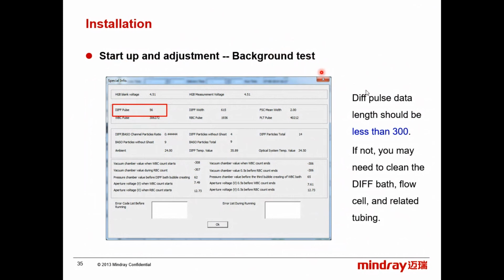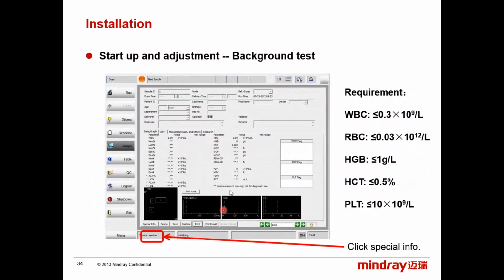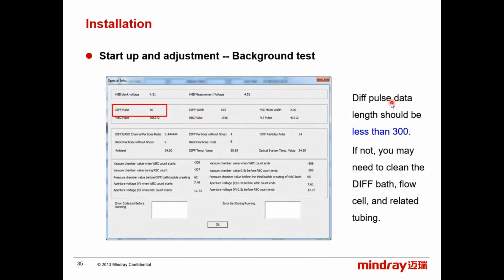All right. For the background test, also the diff pulse data length, because here we do not see it. Here we focus only on the CBC, because these are the CBC parts: absolute value of WBC, RBC, hemoglobin, hematocrit, and platelets. But for the differentiation for the population, how do we know that it is good? For the diff pulse, it shouldn't be more than 300. If more than 300, most probably you have some foreign particles coming with the sheath, or maybe some air bubbles. That is the only thing. It is not electrical interference. It is very highly unlikely to get some interference in the diff path or in the diff channel.